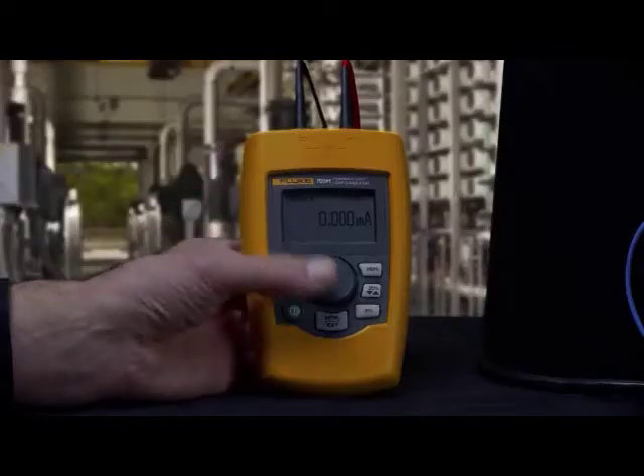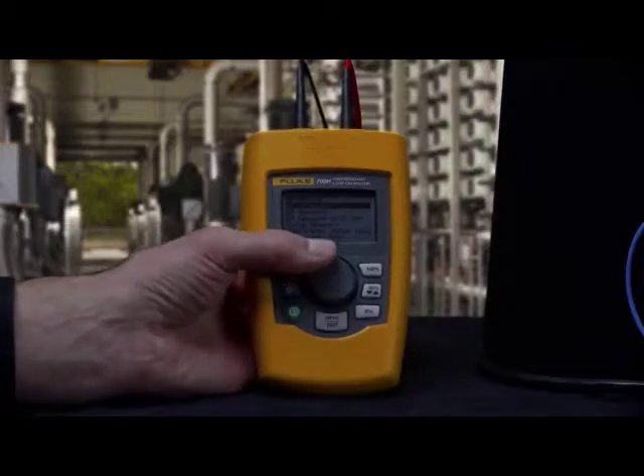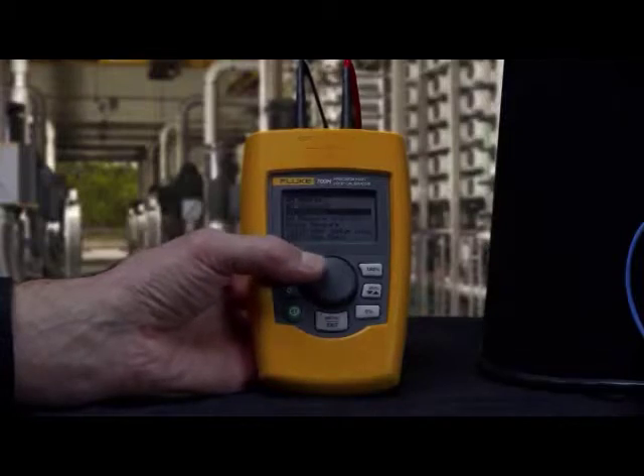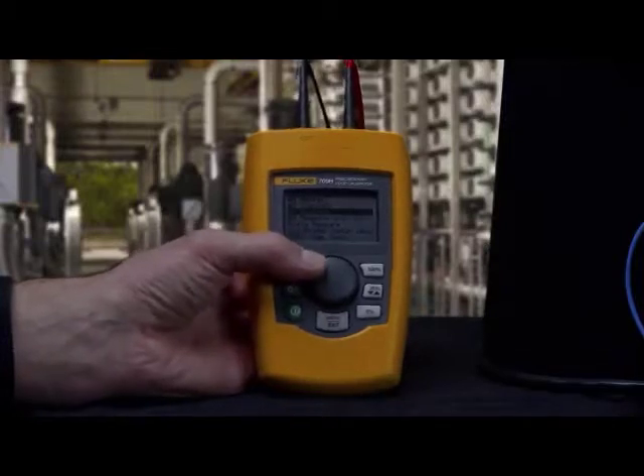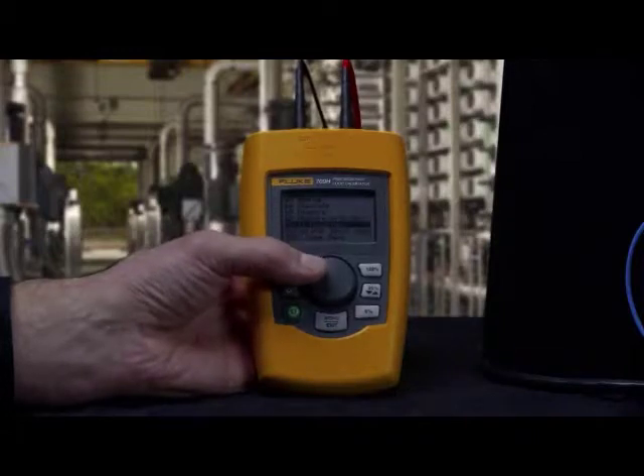Like any good loop calibrator, the 709 can source milliamps, simulate milliamps, measure milliamps, measure milliamps while providing 24-volt loop power, and measure DC voltage and loop power supplies.